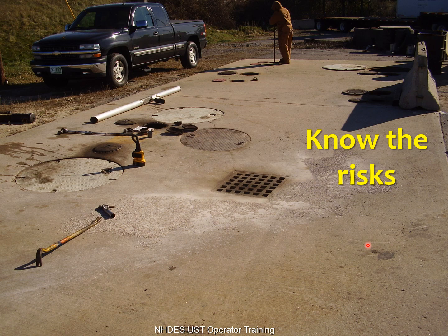Here's an example of a problematic facility. You've got tanks here, fills here, and a catch basin drain right here with a lot of speedy dry around it — so you know there's been a recent release. That looks like it all ran down into the catch basin, and in this particular case the pipe ran right out through this way into a wetlands. That wetlands happens to go into a salt marsh, which happens to go into the river, which is affecting all the clam digging on the seacoast. So they are polluting our food supply — impacting both the environment and nature in our foods.